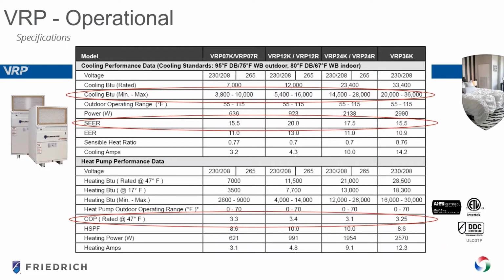And I want to talk to you about performance, because this is kind of where the rubber hits the road here. So let's look at our 1-ton unit. If you look at the performance data there. So obviously on the cooling side, you're going to get the full 1 ton rated at a ton, no problem. Every day, all day, you're going to get a ton of cooling. However, because it's an inverter driven machine, it's an inverter driven fan and an inverter driven compressor. So you get variable speed on both of those. On this unit, you can turn down a 1-ton unit on marginal days to 5,400 BTUs, and you can overdrive the system and it will give you 16,000 BTUs.